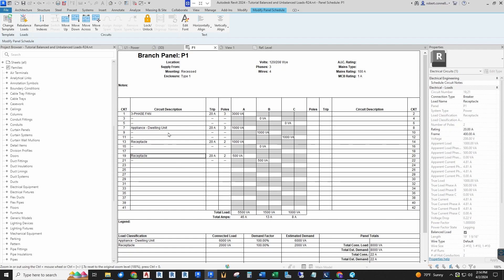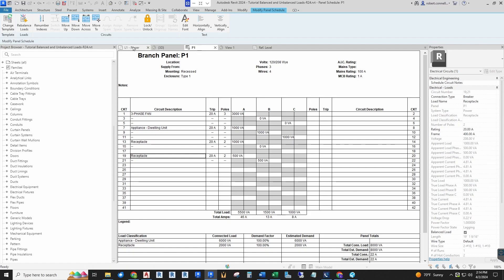And just as a final note, that's just for loads. For electrical equipment like panel boards, transformers, switchboards—they are just passing power through them. They're not actually a load. They will be unbalanced. So that can be confusing as well, and I'll just show you that as an example.